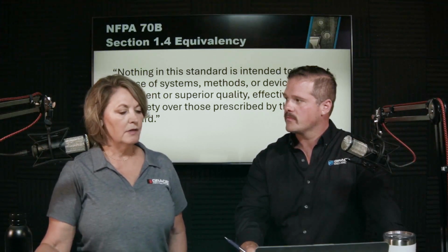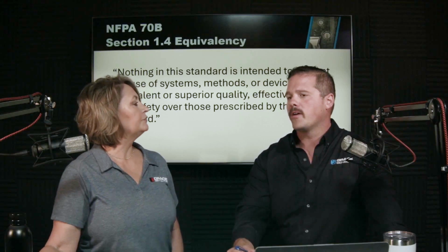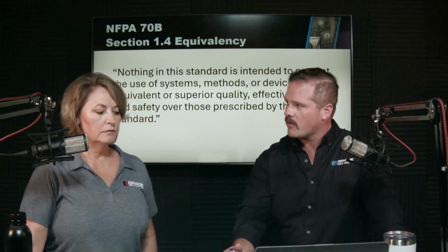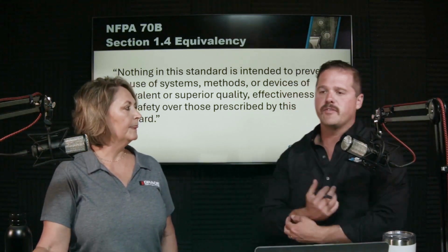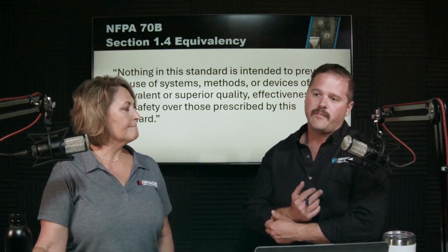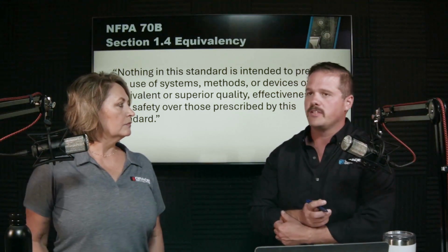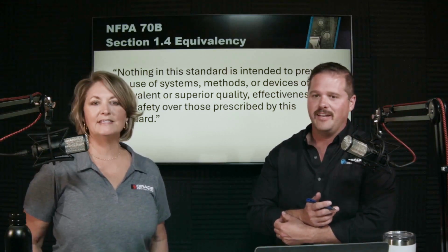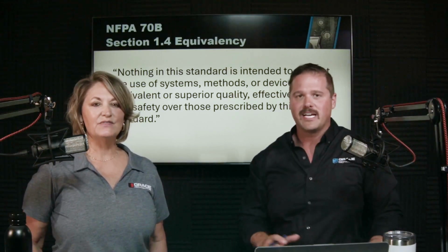These are our default values. It is adjustable from once a minute to once a day, correct? Yes, absolutely. So if you just start collecting a sample one time a day over the year, comparatively to a thermography inspection, that's a 365x increase over the amount of data channels.